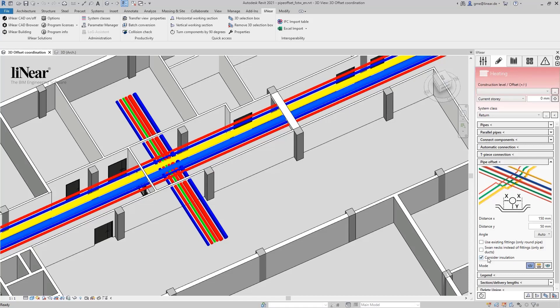Optionally, you can also take insulation into account when determining the offset. We will leave this active here. The command can be used in three modes. The first mode allows you to offset around elements in the actual project. If you want to fix a collision with an object from a linked model, select the second mode, offset around linked element. The last mode is the manual offset which allows you to manually implement the offset in a floor plan.